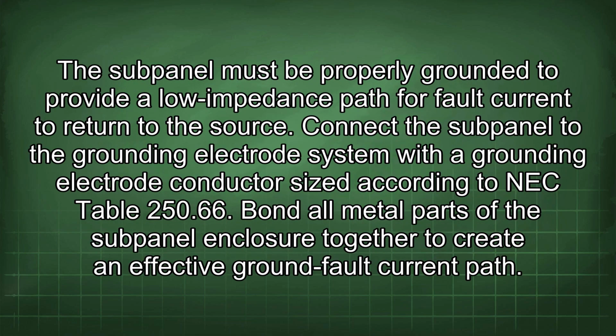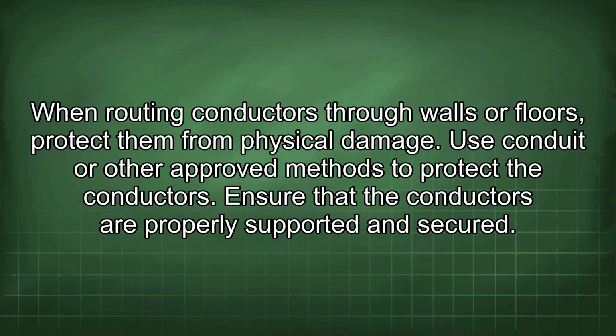The subpanel must be properly grounded to provide a low impedance path for fault current to return to the source. Connect the subpanel to the grounding electrode system with the grounding electrode conductor size according to NEC Table 250.66. Bond all metal parts of the subpanel enclosure together to create an effective ground fault current path. When routing conductors through walls or floors, protect them from physical damage. Use conduit or other approved methods to protect the conductors.